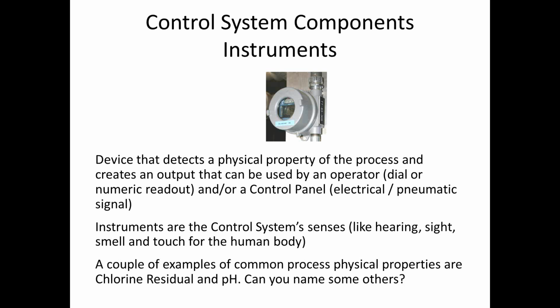It detects a physical property of the process, and it takes that physical property and converts it into an electronic signal that can be used by a control panel or a PLC. There are physical properties such as chlorine residual. You may not be able to tell the difference between 3 parts per million of chlorine and 4 parts per million of chlorine, or a sample that is a pH of 7 or a pH of 8, by looking or touching it. But there are instruments that can do that. There are other types of instruments too: flow indicators, level indicators, pressure, temperature, basically anything that you could use in place of your senses would be an instrument.